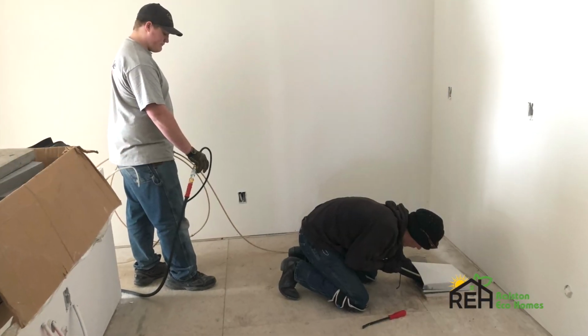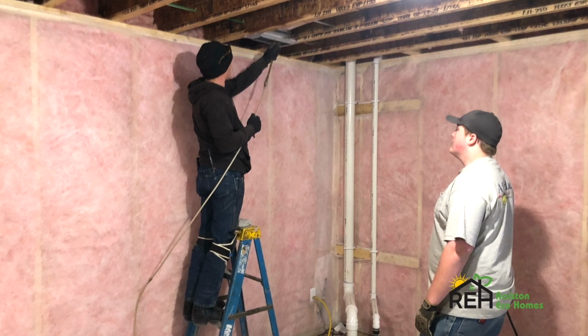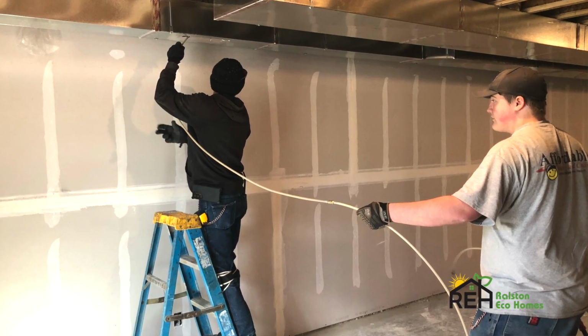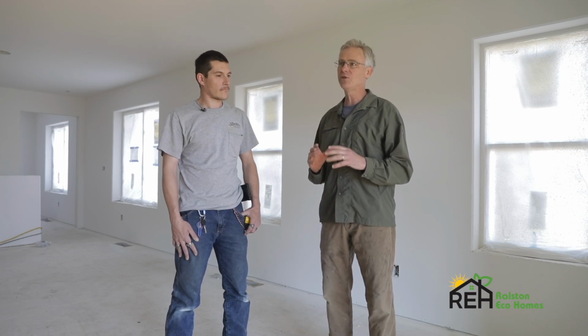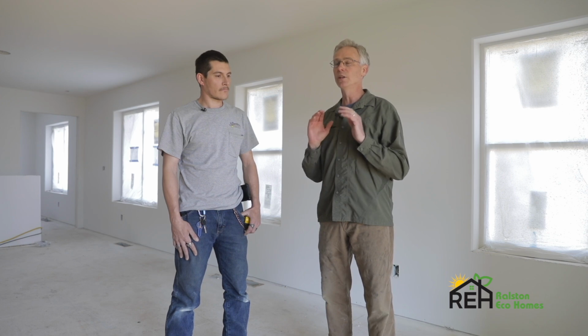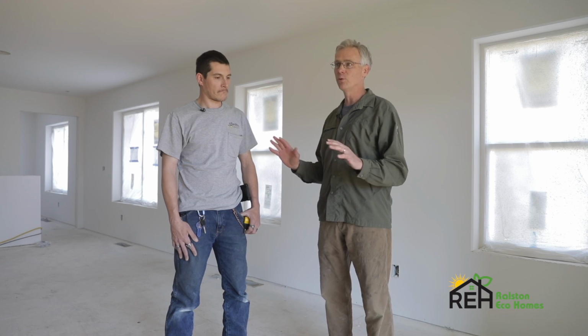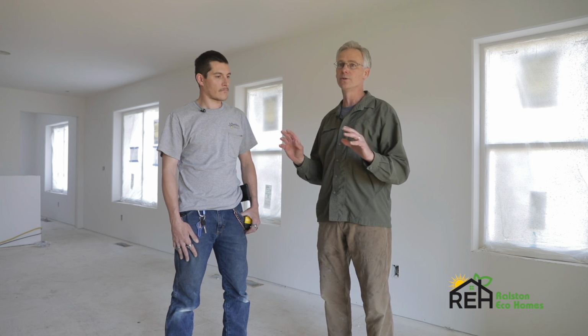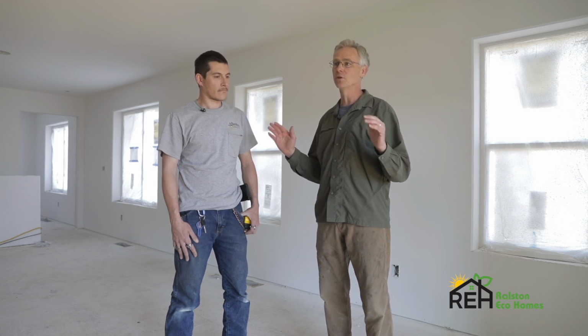So Ricky was here earlier today and he cleaned all the ductwork, and now we're going to be doing duct sealing. And you know, I'm kind of new to duct sealing, honestly, and so I've been giving it some thought. Duct sealing in the most basic form is we're going to introduce a substance into the ductwork so that we can seal leaks from the inside out. So Ricky's going to go down into the basement. He's going to pressurize our entire heating and cooling system, all the ductwork, and then he's going to introduce aerosolized acrylic sealant. And then we're going to monitor the flow through the ductwork, and as that sealant finds all the little holes, the amount of air that we're leaking out is going to decrease over time.